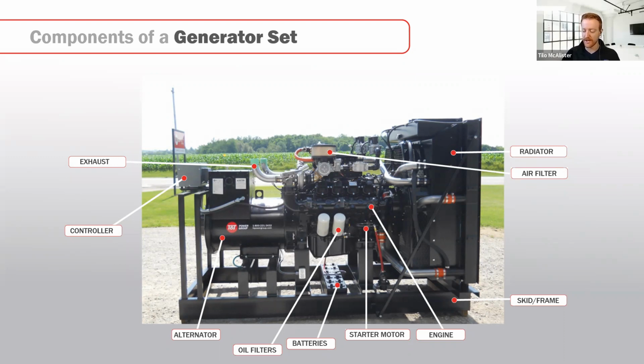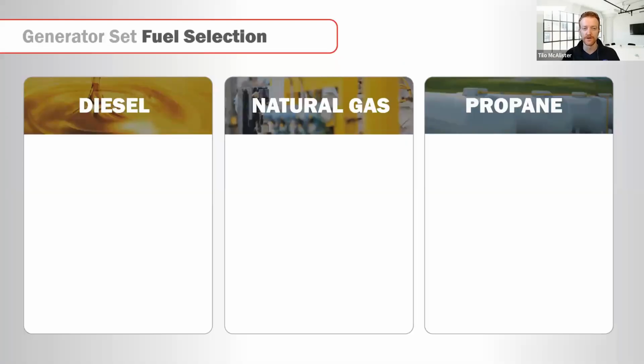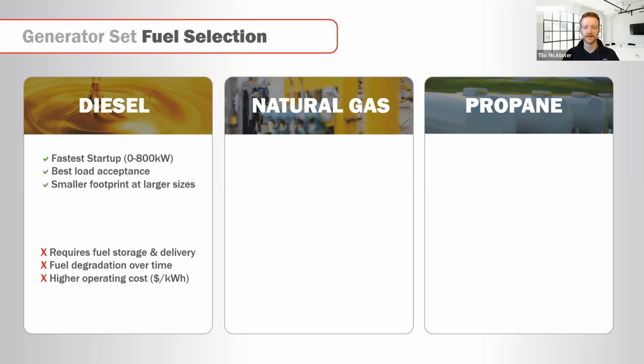So one of the important considerations when you're building or selecting a generator set is the fuel type. And conventionally, the most common fuel for generators is primarily diesel. Then based on your location and availability, we see natural gas becoming increasingly popular for power generation with these units, as well as propane if the natural gas isn't available. Each has its advantages, right? Diesel is often favored because diesel engines have the fastest response time, up to at least around 800 kilowatts, with very good load acceptance. And at the larger sizes, they tend to have a smaller footprint or power density.